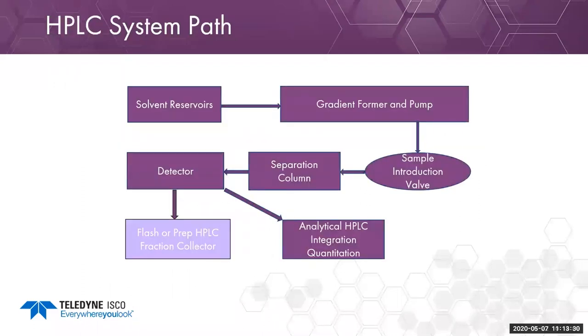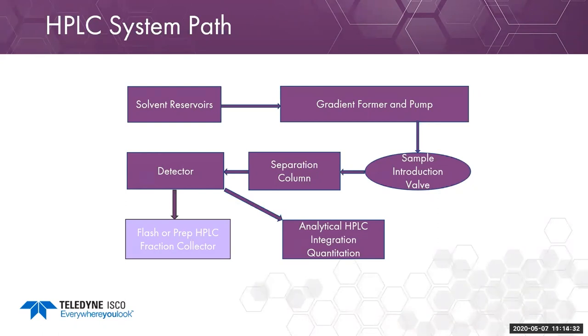A prep HPLC system follows a similar path to flash or analytical HPLC systems. We have solvent reservoirs with A and B solvents, a gradient former and pumps mixing solvents to deliver a certain percent solvent strength, a sample introduction valve where improvements to separations can be made, a separation column, and a detection system to trigger fraction collection or enable integration and quantitation.